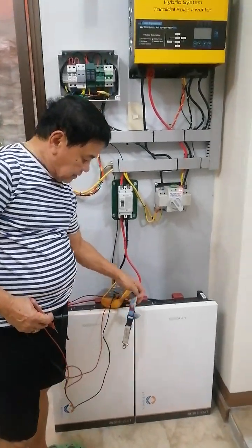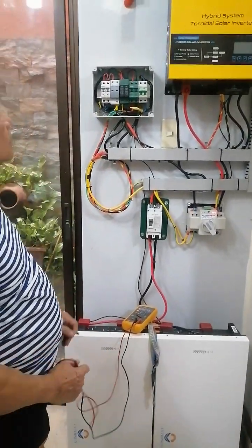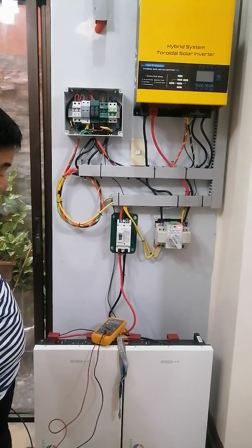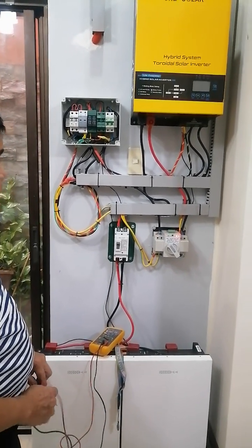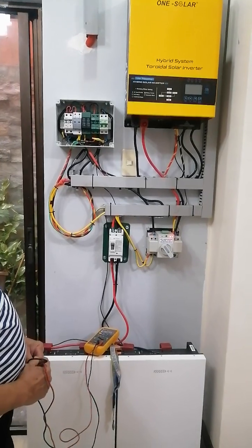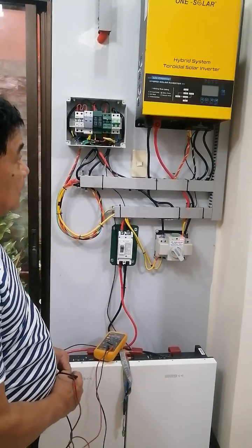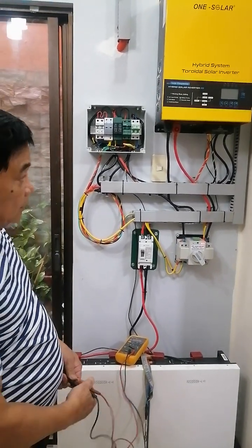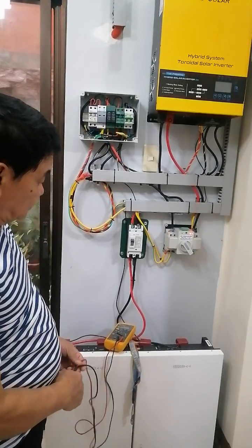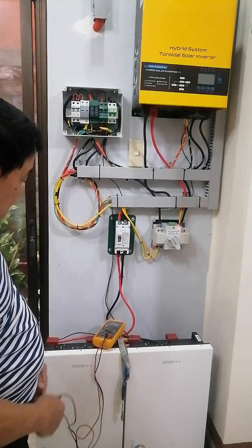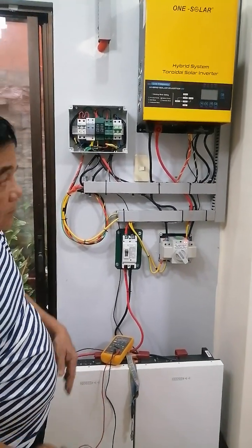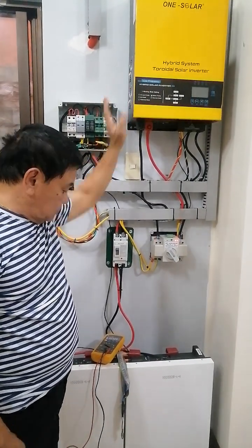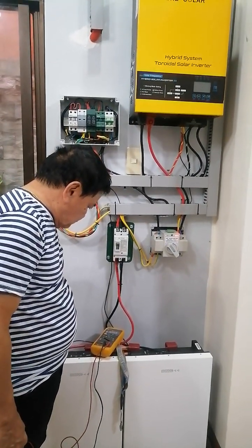Right at the project site, the 8 panel, 48 volts up to 51.2 volt battery is off. That is from the last performance of it was on battery mode, and since, as we had mentioned, no AC input, that's why when the battery depleted, the operating system of 48 volt is disabled. So right now, we are powering on now. We just arrived.